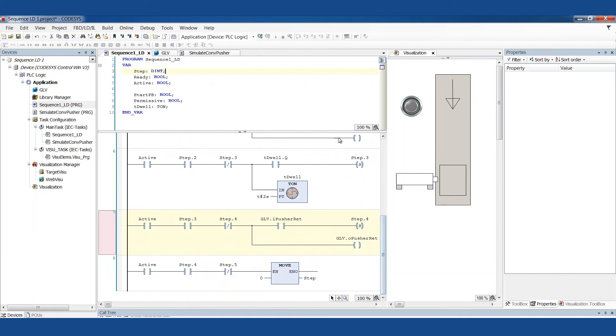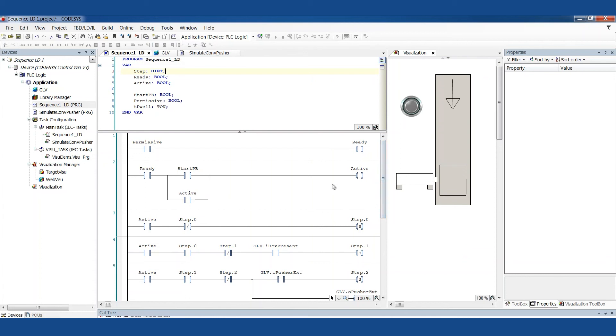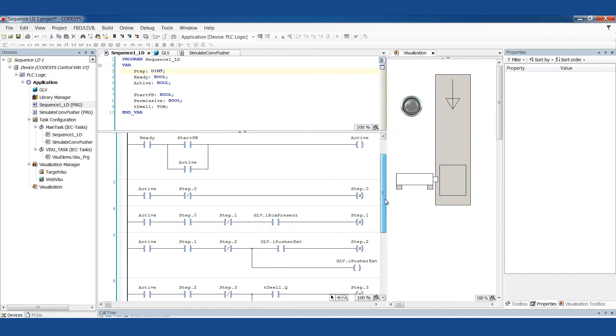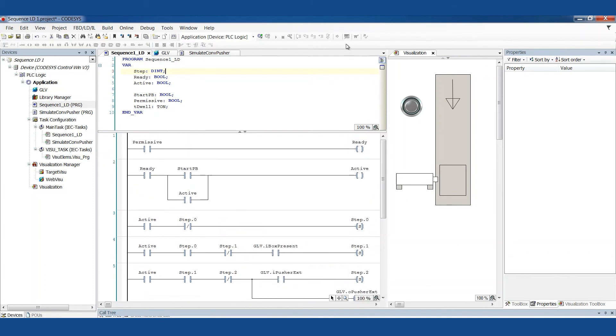Another thing I want to point out before I leave here is this is not really robust the way it is right now. And it's just because it's an example. It's not because of this type of structure. This type of structure can be robust. Right now, if there were a fault or if I decide to clear the permissive, this just stops wherever it is. The step bits aren't cleared out. In a real situation, maybe I'm happy with this machine just starting back up wherever it left off.